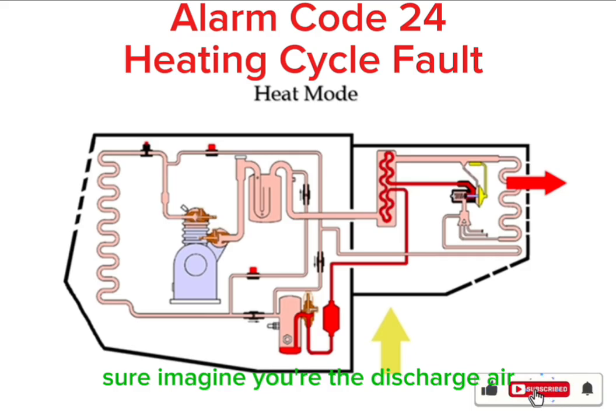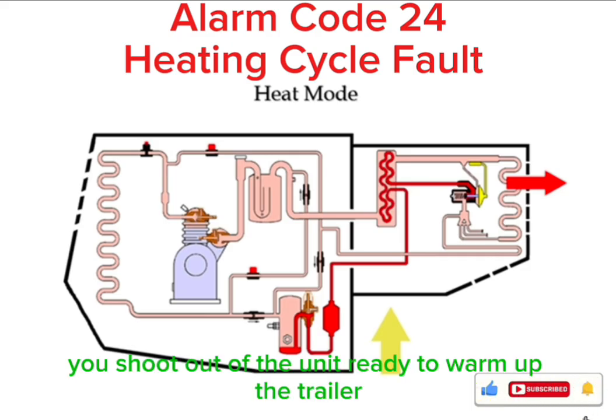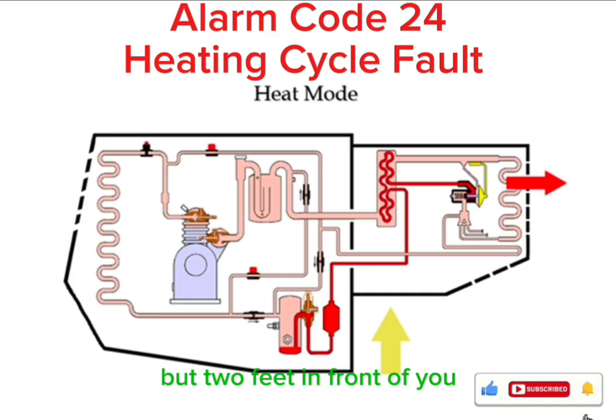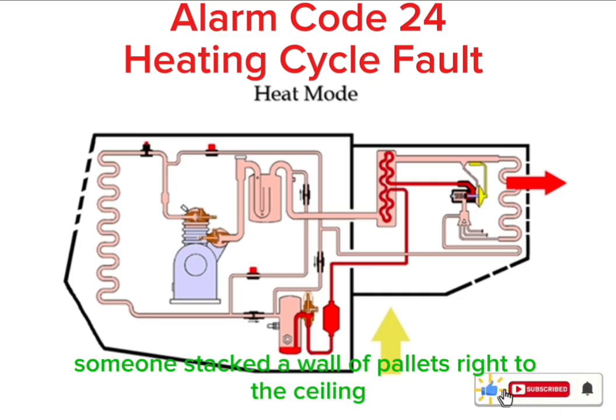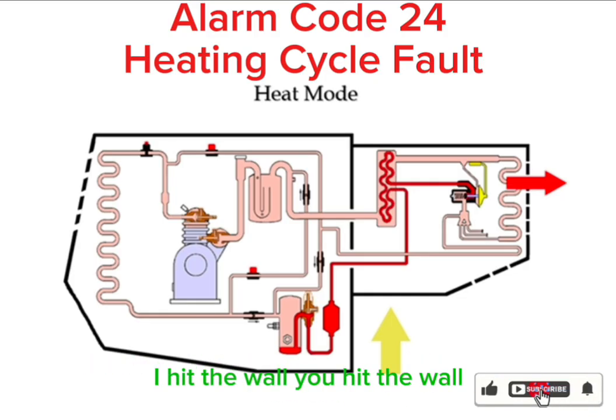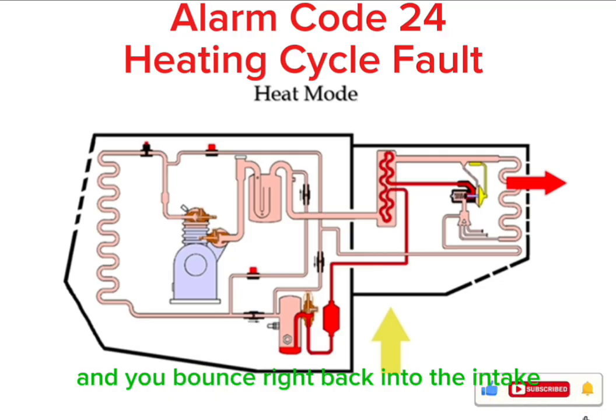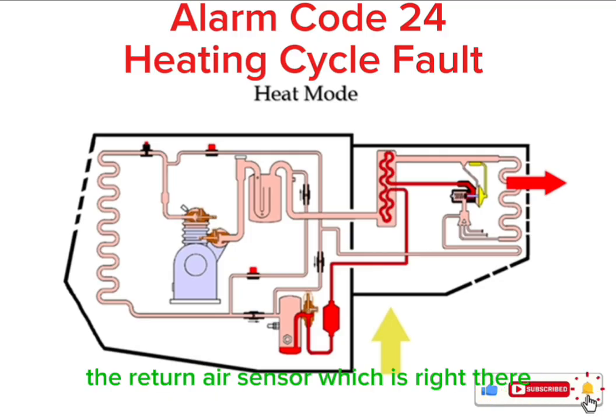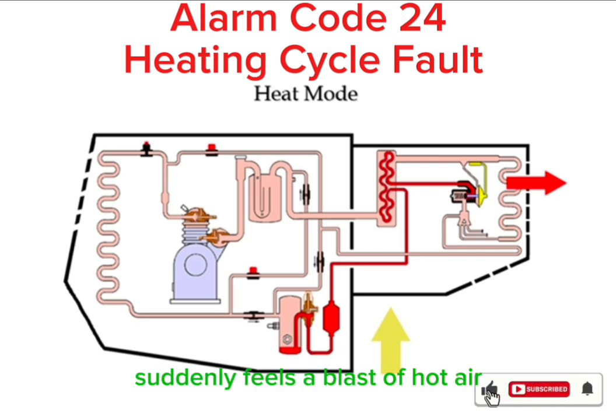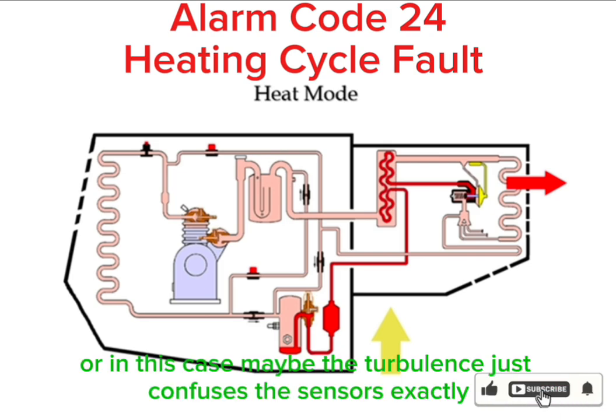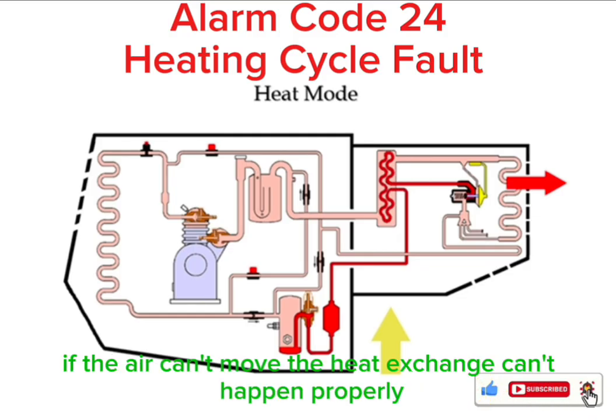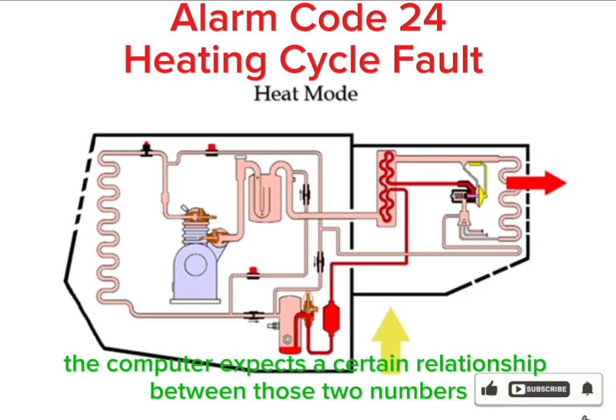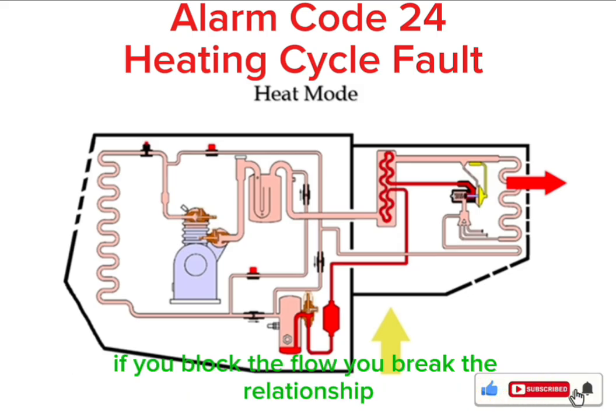Sure. Imagine you're the discharge air. You shoot out of the unit, ready to warm up the trailer, but 2 feet in front of you, someone stacked a wall of pallets right to the ceiling. I hit the wall. You hit the wall, and you bounce right back into the intake. The return air sensor, which is right there, suddenly feels a blast of hot air, even though the rest of the trailer is freezing. Or in this case, maybe the turbulence just confuses the sensors. Exactly. If the air can't move, the heat exchange can't happen properly, the sensors get erratic readings, and the computer expects a certain relationship between those two numbers. If you block the flow, you break the relationship.